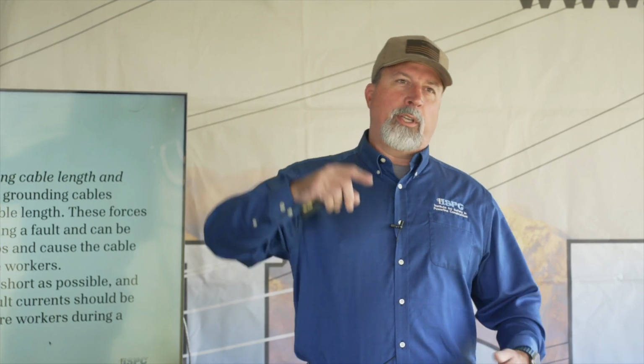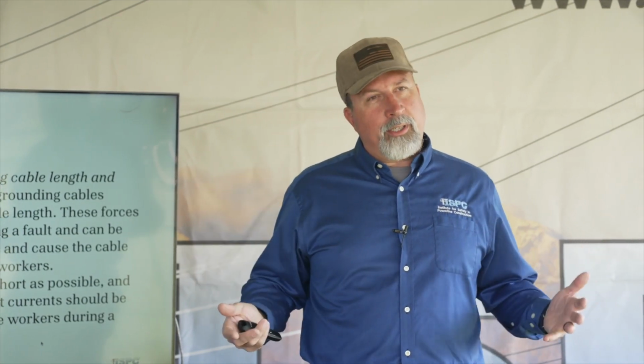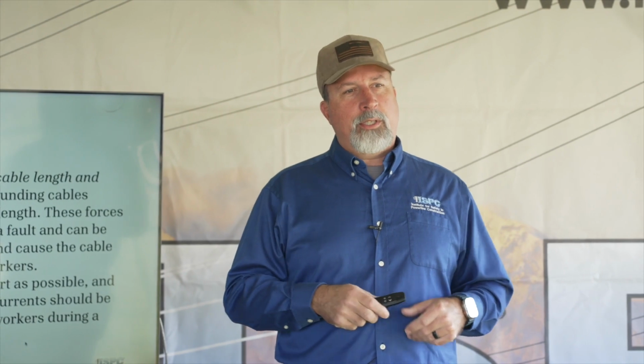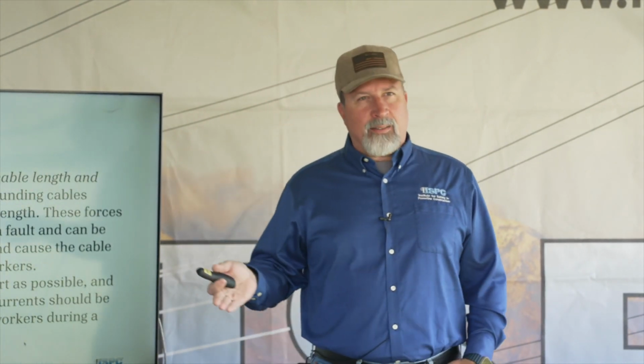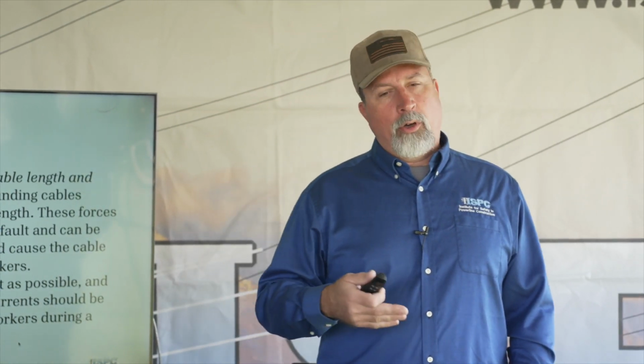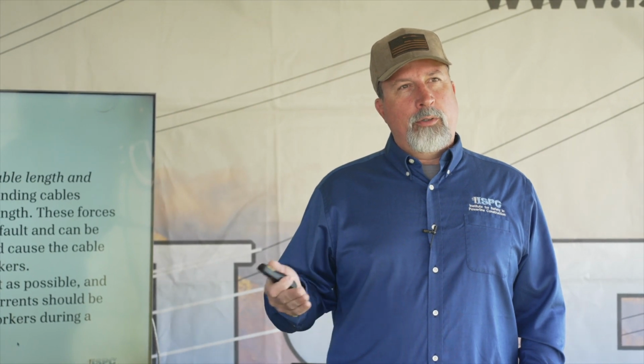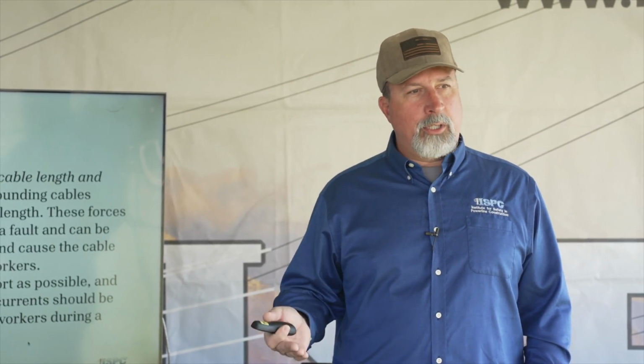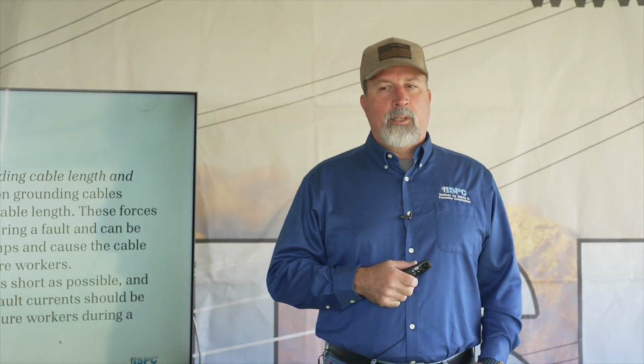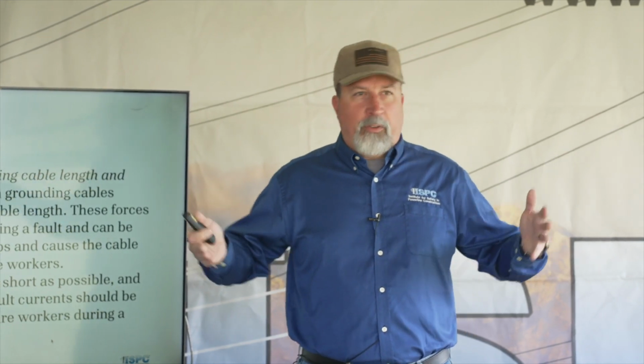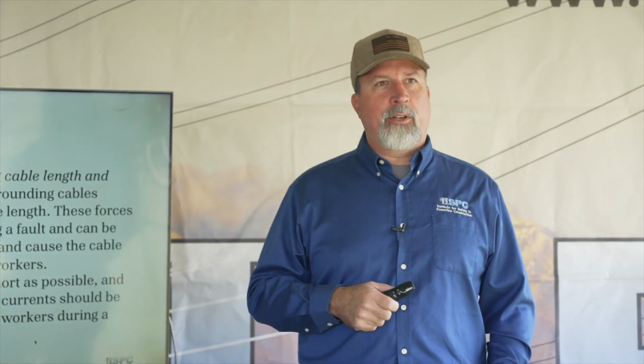But due to using long cables and not securing them properly, you're going to see the violence that occurs when that fault happens, right? And so you always hear when you install your grounds, and OSHA tells you this, your cable length should be as short as possible, right? And the answer you always get is, well, 15 feet's the shortest ground I carry on my truck.